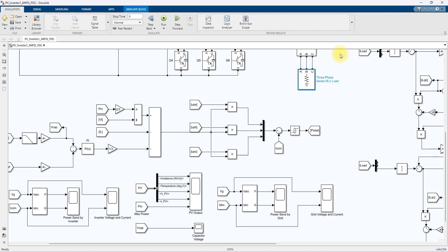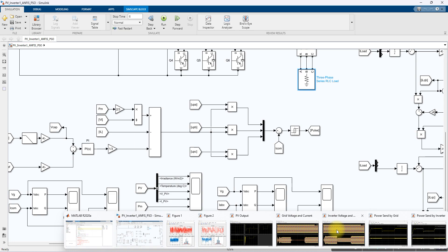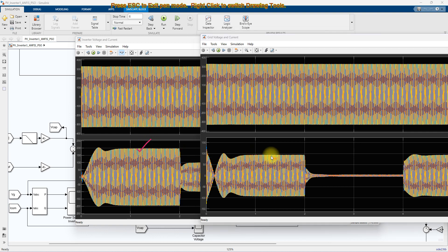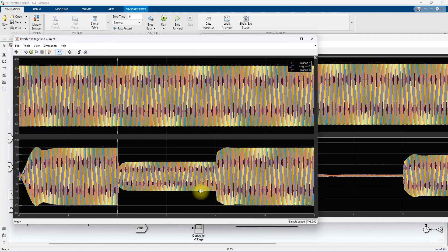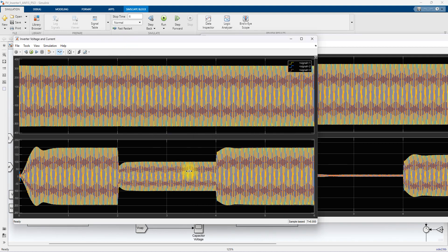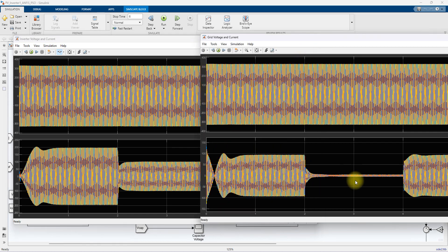The 50 kilowatt load is supplied first, and the remaining power is sent to the grid. With inverter current at 200 amps, the grid current is around 96 amps peak — equivalent to around 46 kilowatts — which is the excess power sent to the grid. When irradiation changes to 500 W/m², the inverter current drops to around 100 amps peak, and the grid current goes to zero because all PV power is used to supply the local load with no excess remaining.